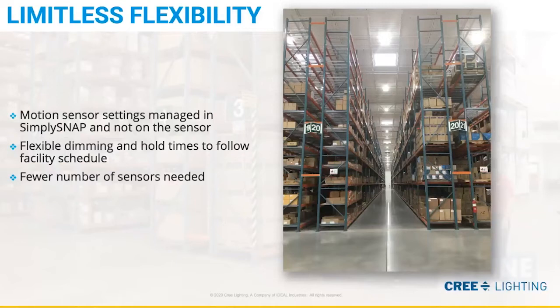works with motion sensors. We talked earlier about circuit switch control, where a light switch or a relay panel is turning power on or off to a group of lights. If you think about the way occupancy sensors have been used in legacy wired controls environments, they do provide additional flexibility where individual lights are controlled by a motion sensor. The problem with that approach is it's not nearly flexible enough. The settings on each of the motion sensors are hardwired and can't be changed after the install. So the customer is stuck with whatever the hold time and the dimming levels that are configured on the sensors.